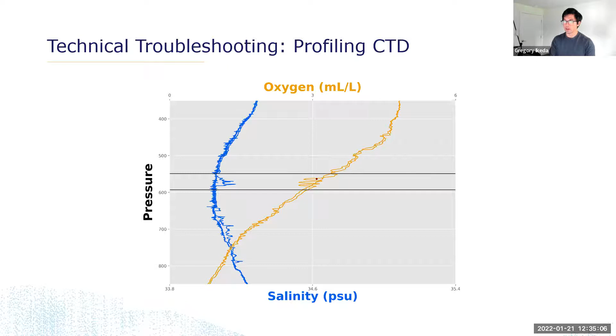So once again, having additional parameters gives you more clues for technical troubleshooting to find out why your data look the way they do. This was particularly helpful when testing our prototype ISFET pH sensors, the SeaFET and SeapHOx pH sensors. We know these sensors respond to chloride ions in seawater, so we need to measure salinity to account for that and optimize data quality. Knowing salinity helps us understand whether a shift in pH is due to the sensor responding to actual pH changes, or because salinity is changing.